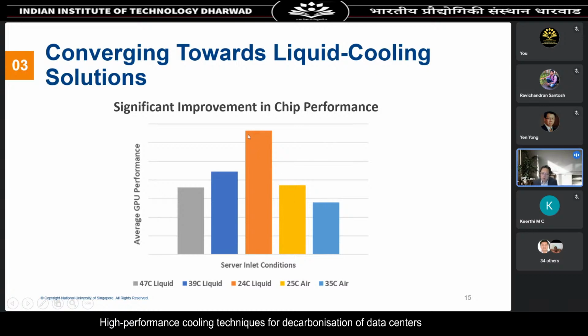This shows that associated with better management of your chip temperature, your chip operates very efficiently, and that translates to a much improved chip performance. If you increase your inlet temperature for liquid cooling from 24 to 39, you see a drop in GPU performance, from this level to this level, but it's still higher compared to the 25 degrees air cooling baseline. Likewise, if you further increase the inlet temperature for liquid cooling from 39 to 47 degrees Celsius, there's a slight further drop in average GPU performance, but compared to the 25 degrees air cooling baseline, these two are actually comparable.